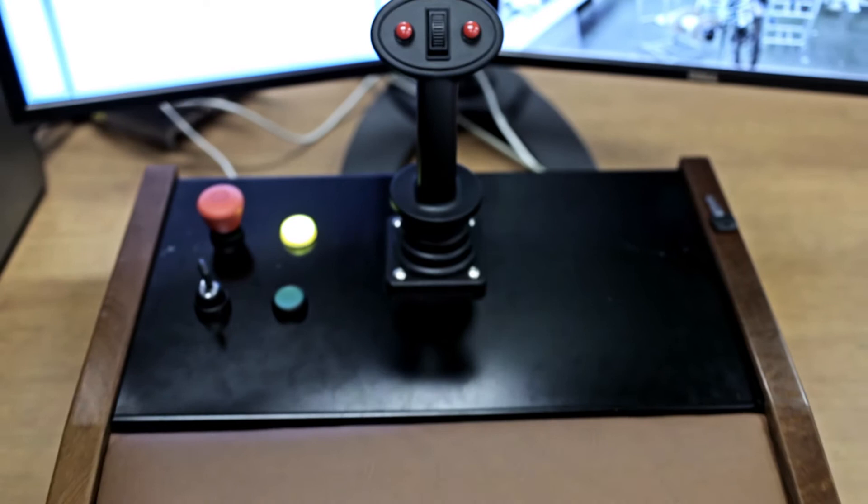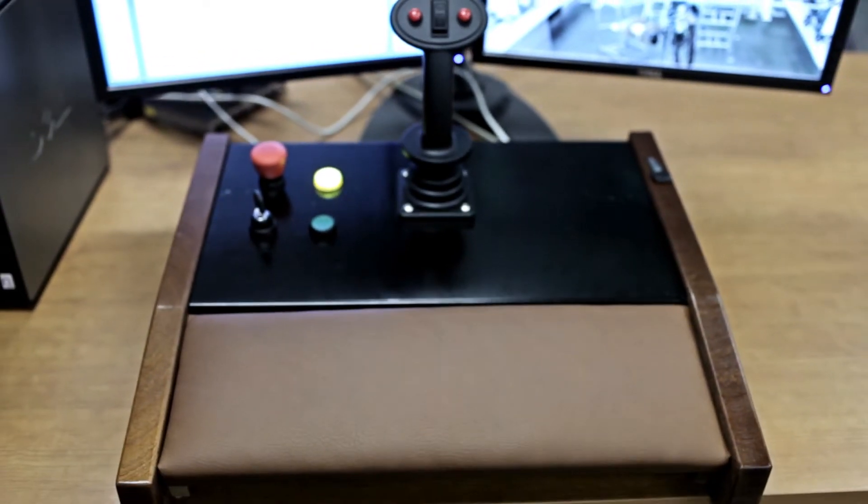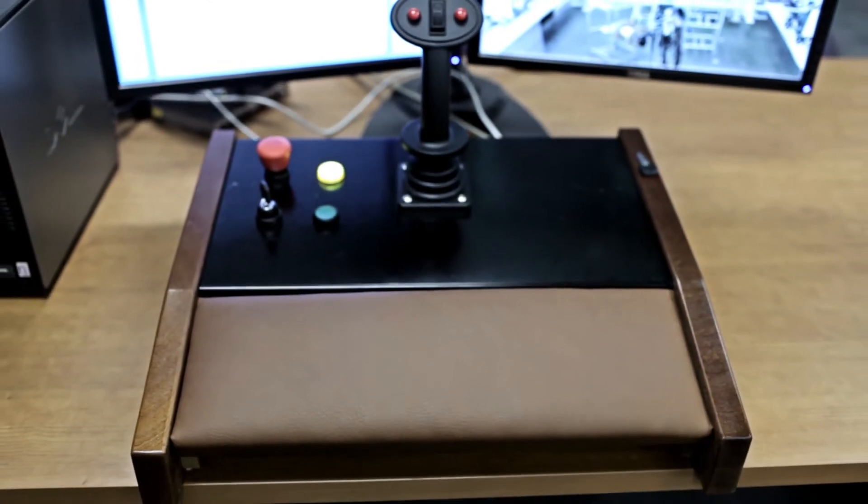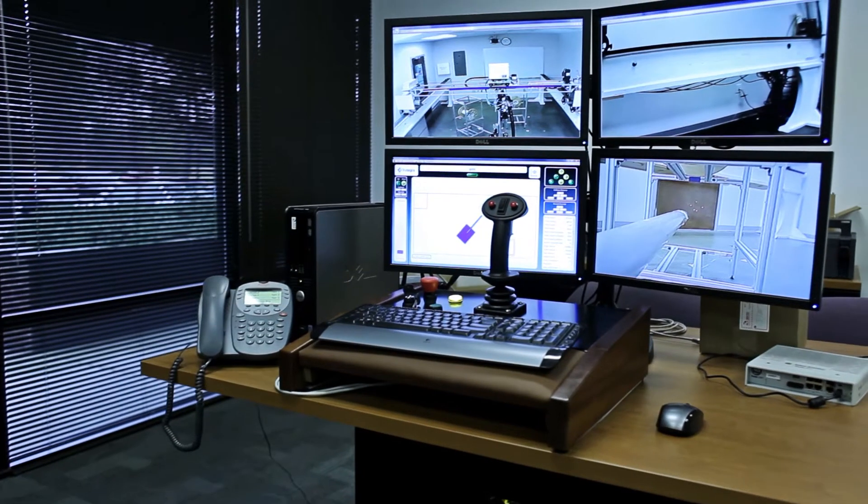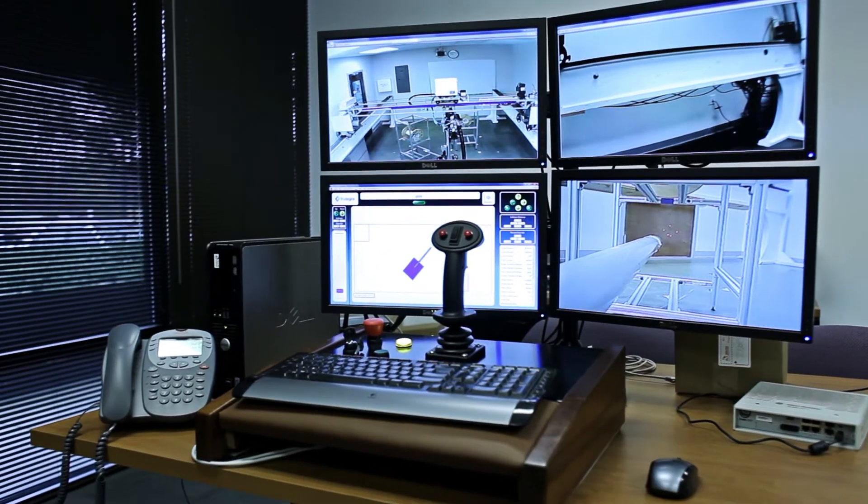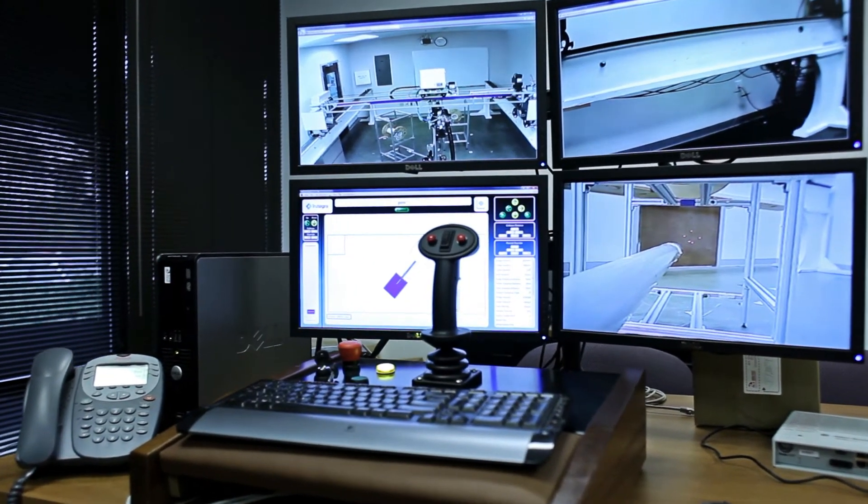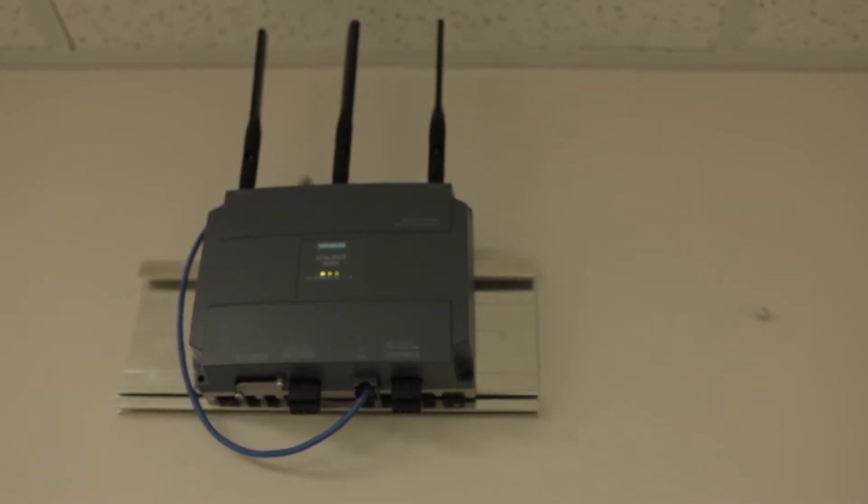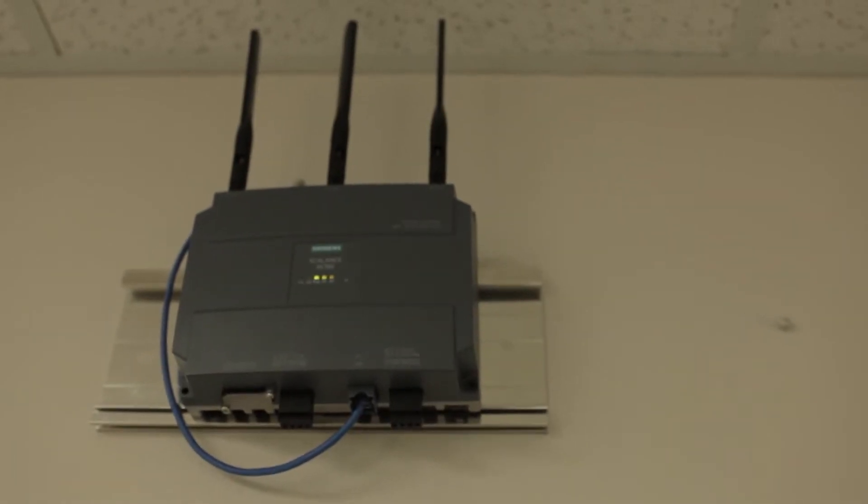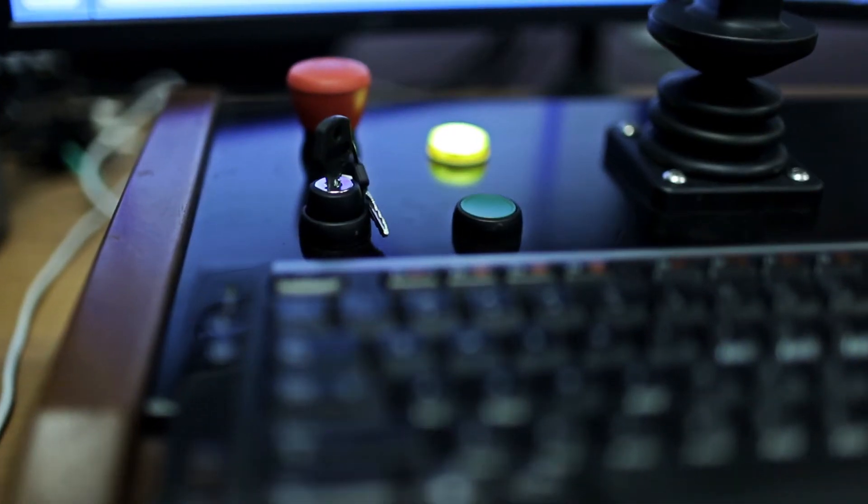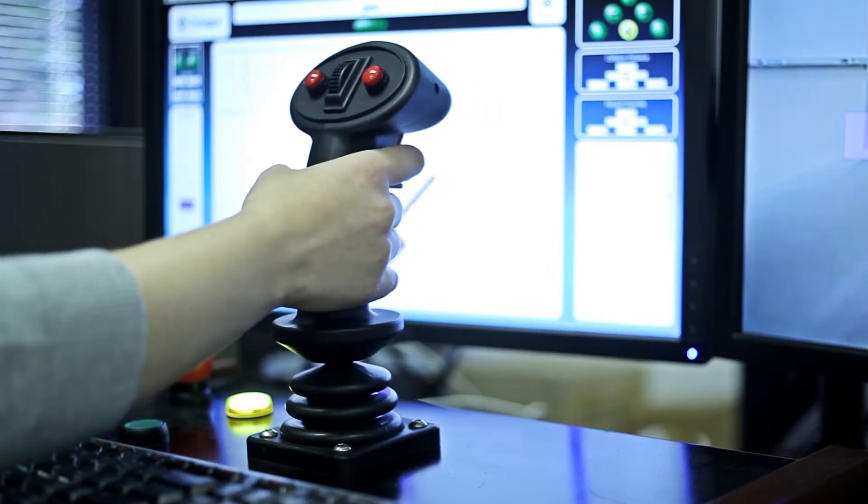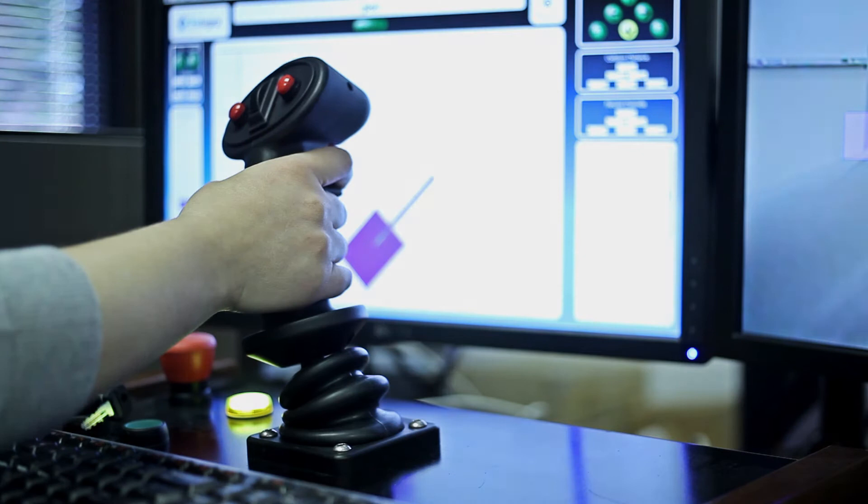An ergonomically designed operator's console allows the operator to drive the crane remotely. The console connects the crane's control system wirelessly or by wired ethernet. We use safety rated remote I.O. to achieve SIL-2 or SIL-3 safety ratings where required.